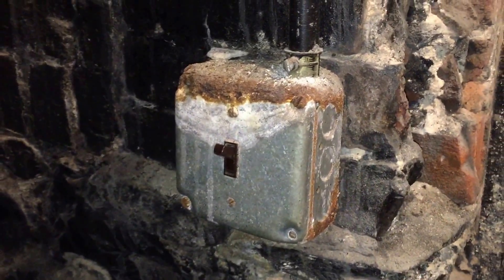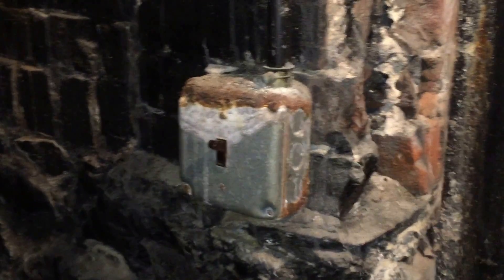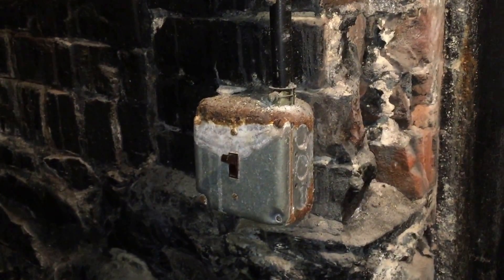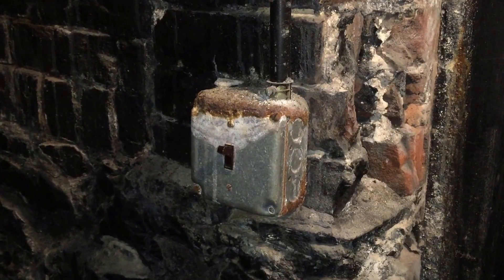This box should probably be relocated to a more dry location, and maybe with something that's non-metallic so it won't rust up again. This is Russell Blank, NEC consultant for EC&M magazine.